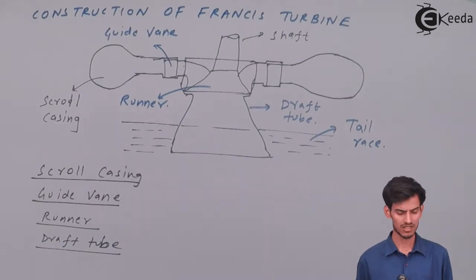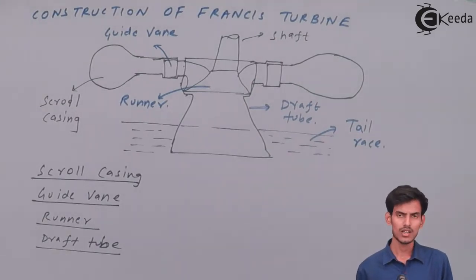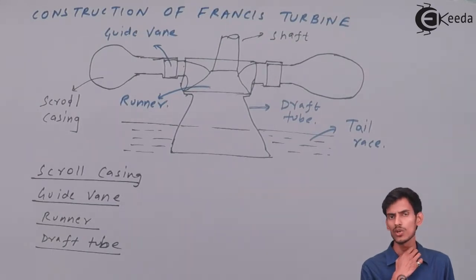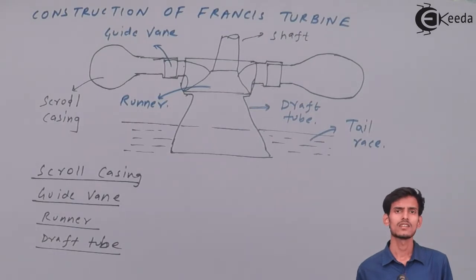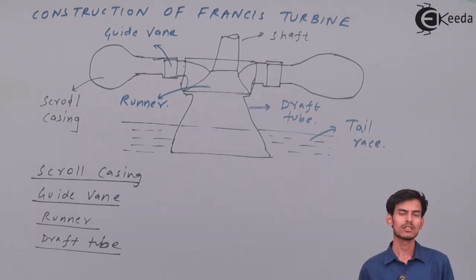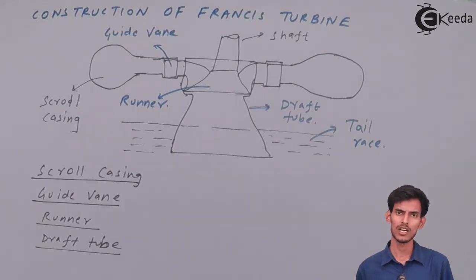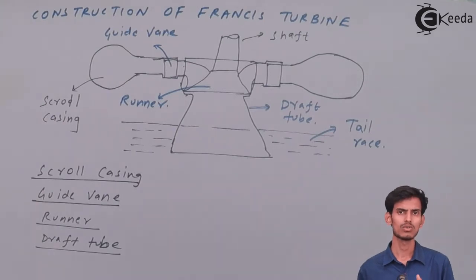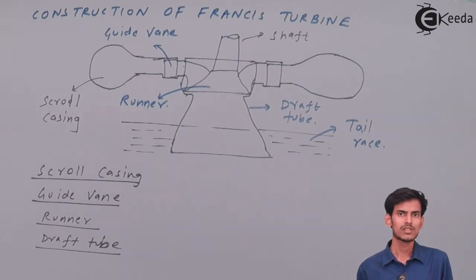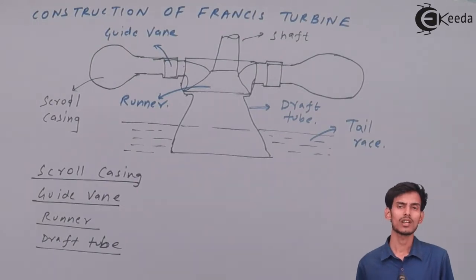These four are the main important parts of the Francis turbine, each with a specific use. The scroll casing guides water into the guide vanes, and is designed so that its cross-sectional area goes on decreasing as water passes through, which helps maintain constant velocity. After the scroll casing, water moves into the guide vanes — aerofoil-shaped structures that direct water into the runner without shock or friction. As water enters the runner, it creates impulse and momentum, pushing the runner to rotate and generate power.